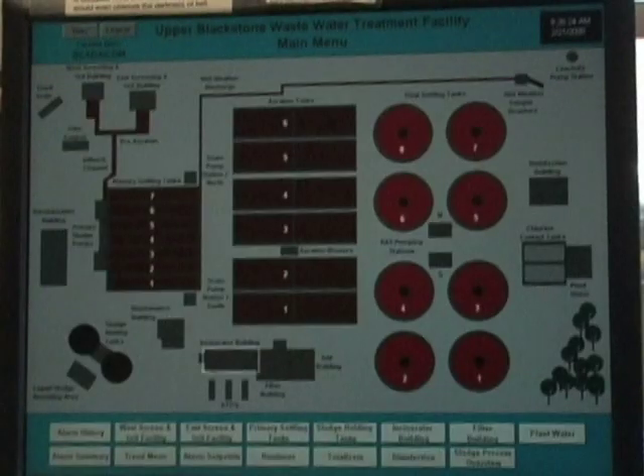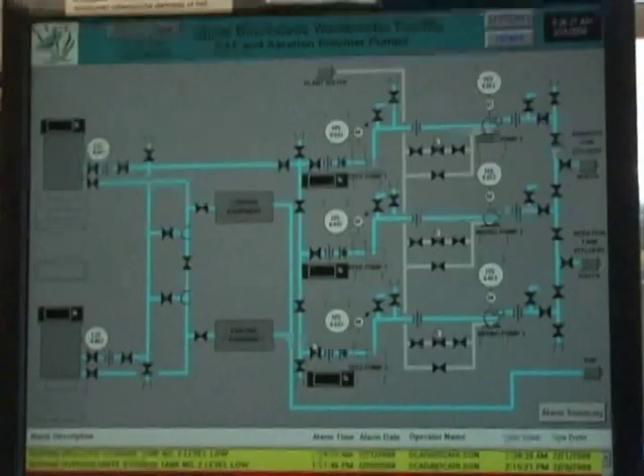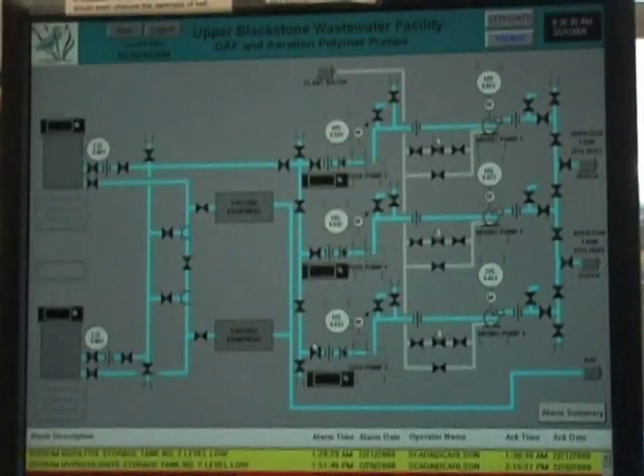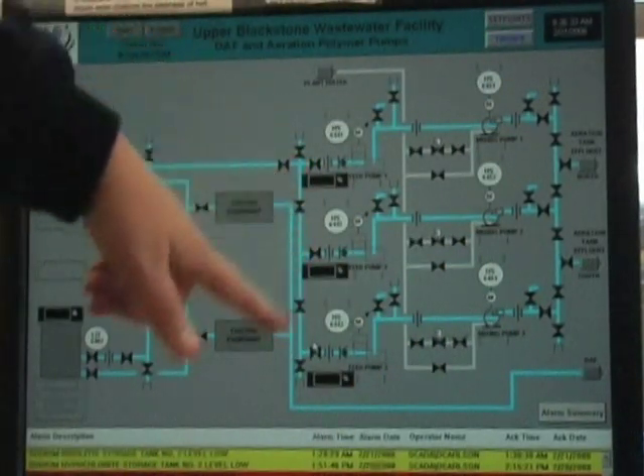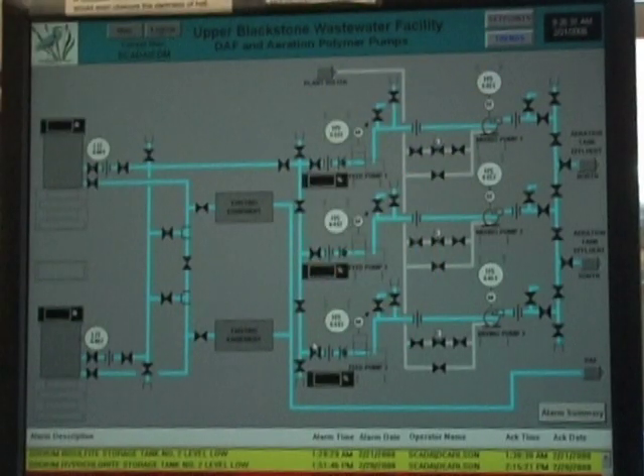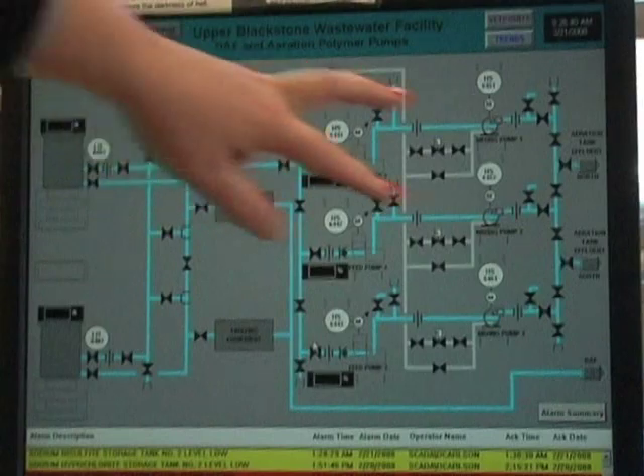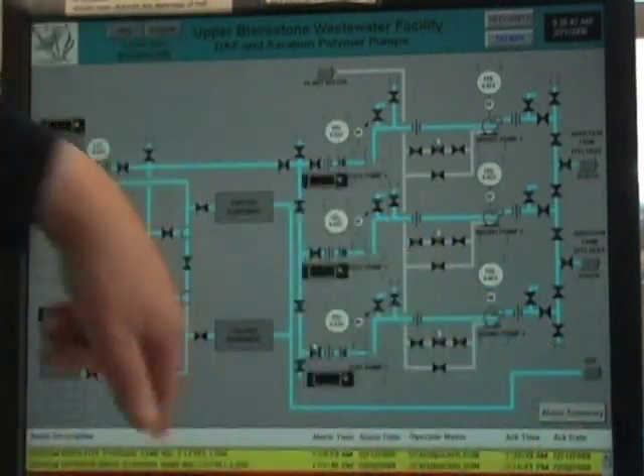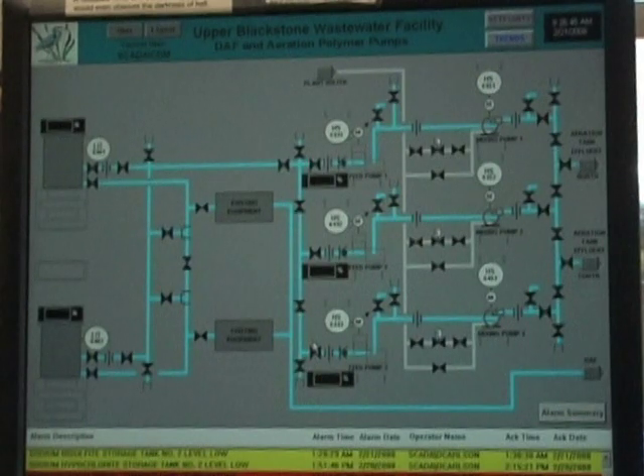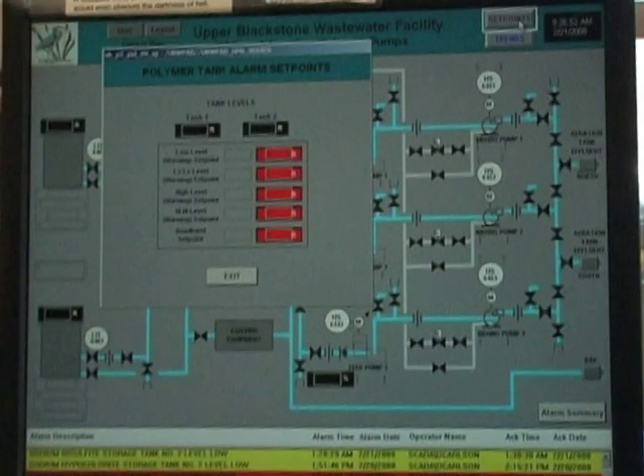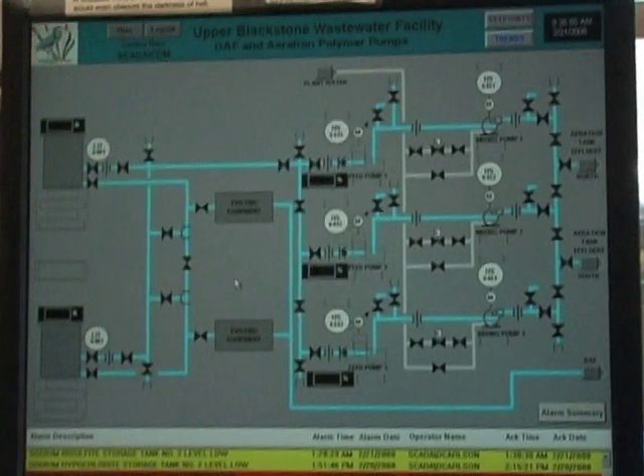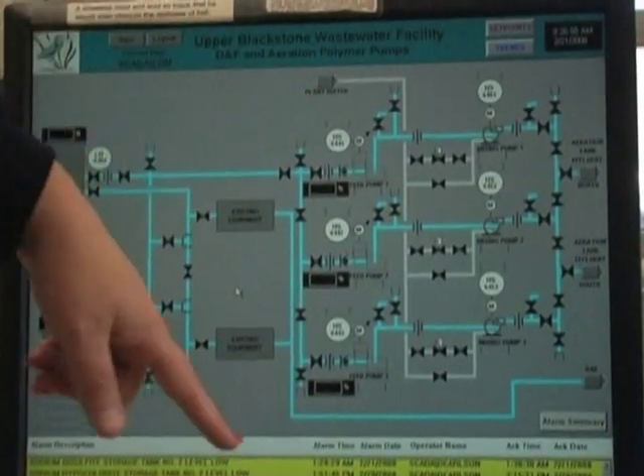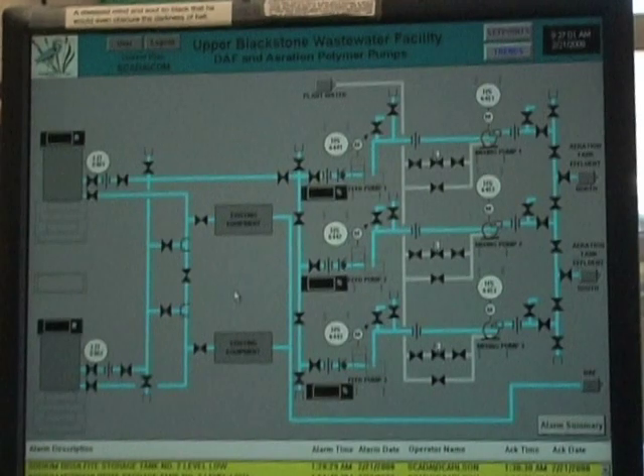So then from here, we're going back to the filter building, and we're going to bring up the new polymer screen. We have the 2 tanks, we have the 3 feed pumps and the 3 mixing pumps. The feed pumps are speed control, the mixing pumps are single speed. These pumps will be feeding the new aeration tank system, but you do have the existing polymer that feeds the DAF. Again, you have the set points for the tank levels so that you get high and low alarms if necessary. We'll have the information for the feed pumps, whether they're in local or remote, whether they're running or not, and what speed they're running at. If they have any alarms, those will show as well. That's pretty much the system right there.